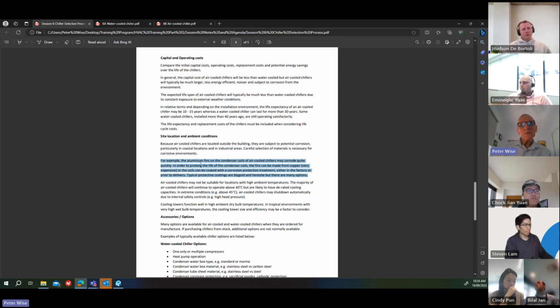In order to prolong the life of the condenser coils, we're talking about the fins really. The copper tubes are okay. It's the aluminium fins. The fins can be made from copper, and that's very expensive. You can ask for an option from the suppliers for copper fins, and they'll be happy to give you the option, but it'll cost a lot more.